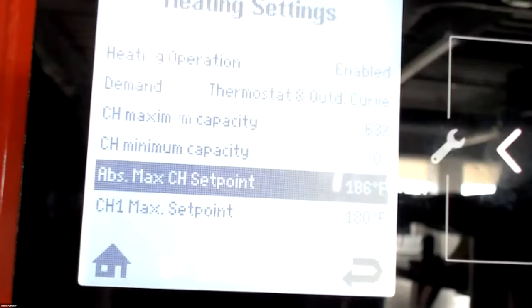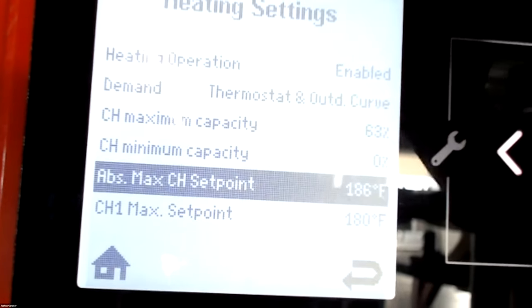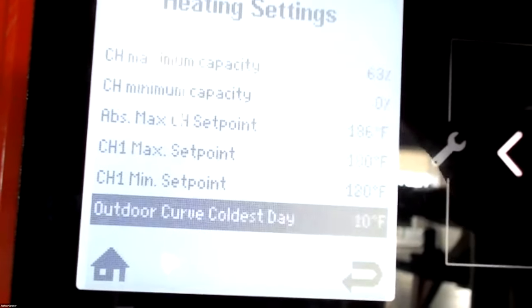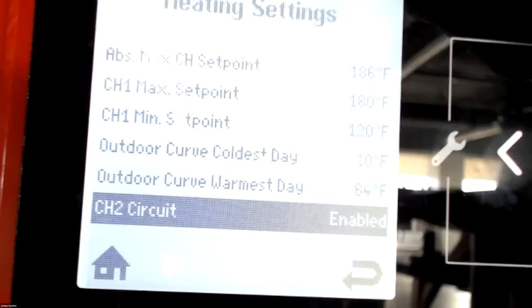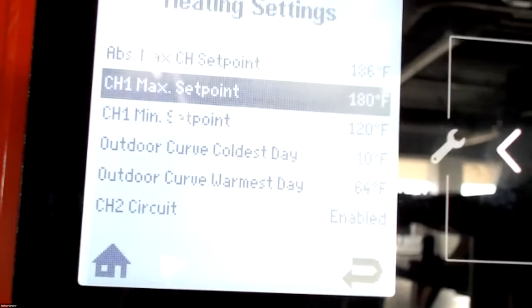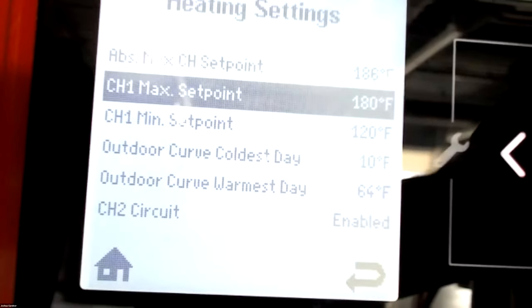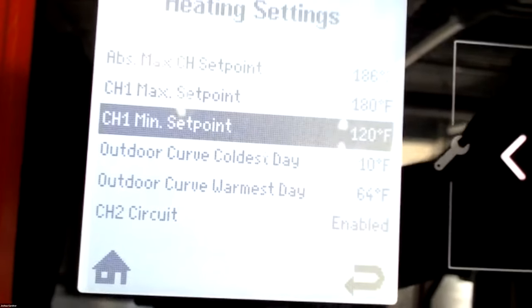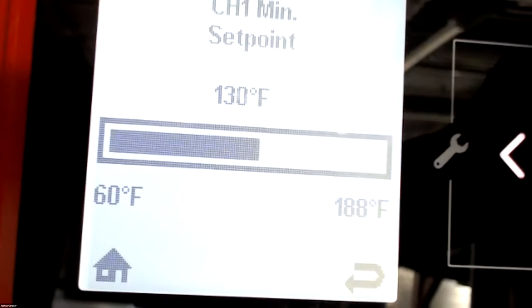Our absolute max set point, 186. And then let me just scroll down a little bit. So this is where we can completely customize that curve. So CH1 max set point 180, this is that curve that we set earlier. So again, like I said, if we're doing a baseboard job, I'm going to go into that CH1 min set point, and I'm going to bring that up to say 160.